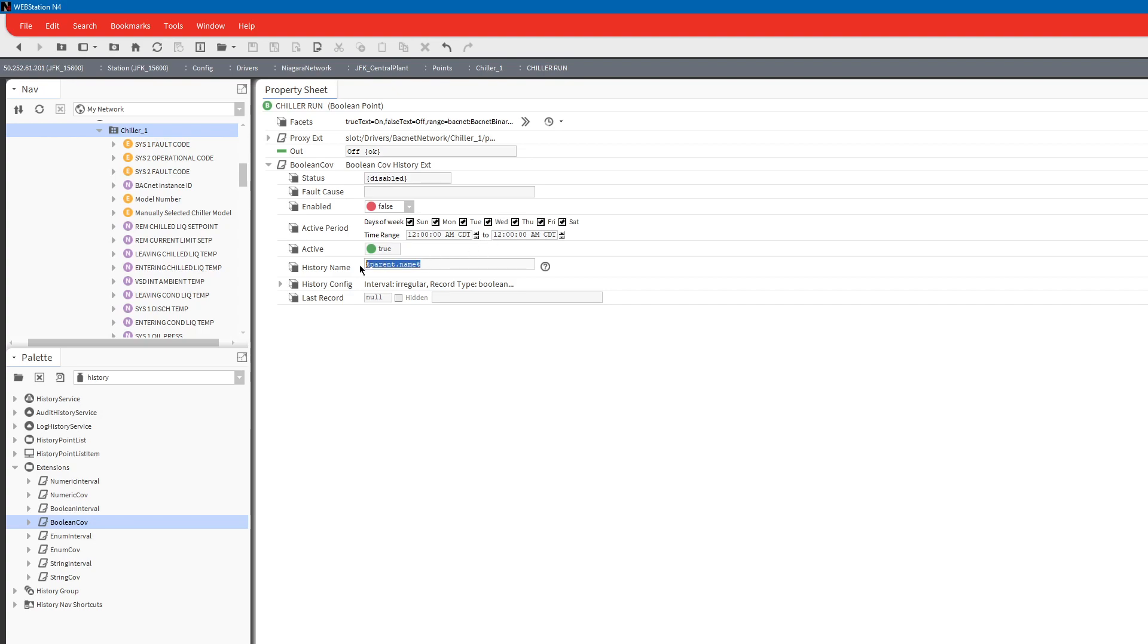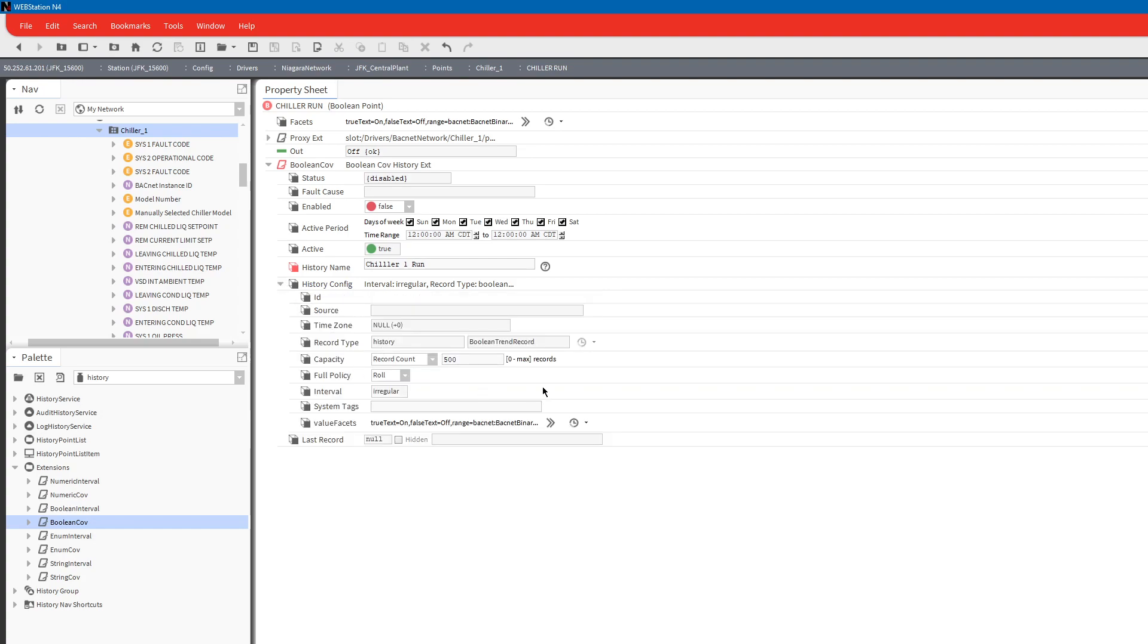You can just rename the history however you want, which is usually how the customer wants it. For instance this one they wanted chiller one run. We're going to configure our histories right now. Since this one is on a computer we'll make this fifteen hundred counts, have it roll automatically when it gets up to that point, go ahead and enable so now it's going to record 24/7.